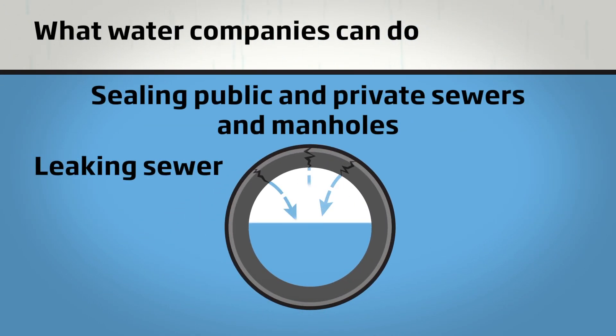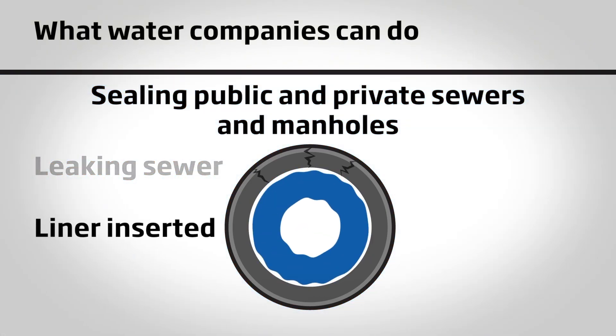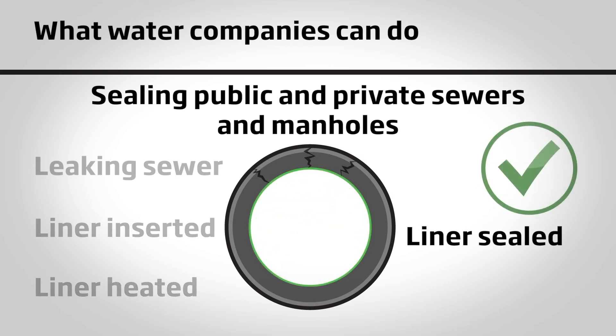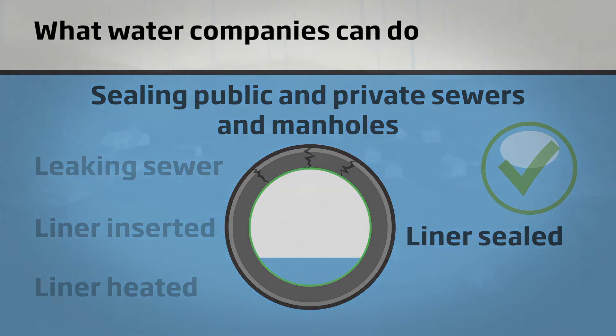Our long-term goal is to make the sewer system watertight. This is achieved by lining sewers in the highest risk areas. We often use no-dig technology to make as little disruption as possible. This requires an ongoing programme of inspections to find any cracks and then lining the sewers to make the assets watertight, to reduce groundwater seeping into sewers.